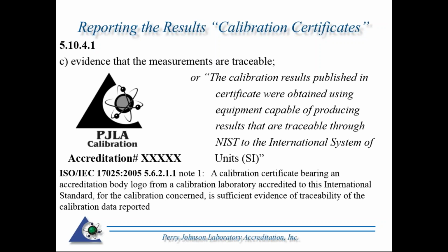So if we see a calibration logo that's specified within the requirements in SOP 3, and the example I have in here, say this was on a calibration certificate, this is stating that this is under their accreditation, hence the calibration is traceable. The assessor should also verify, just because there's a logo on there, that the organization that did the calibration could be accredited, but they may have to verify that they are in fact accredited to do the specific calibration.